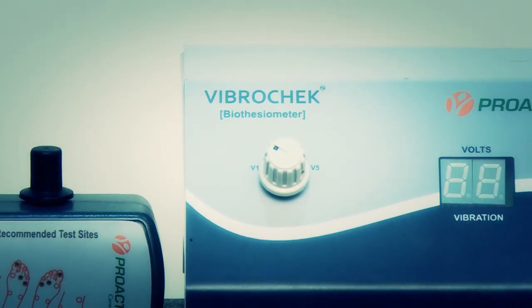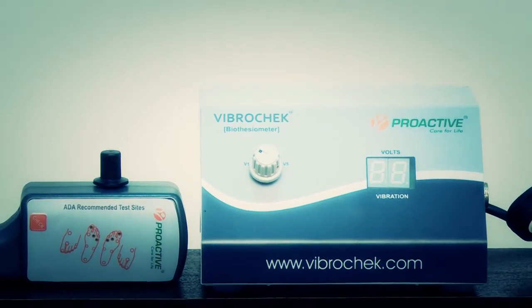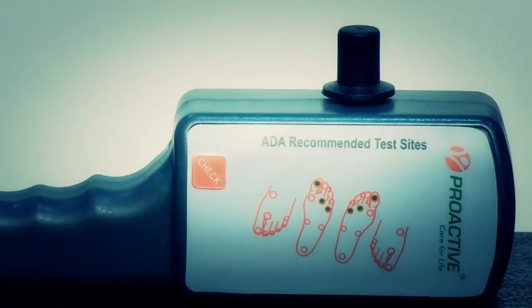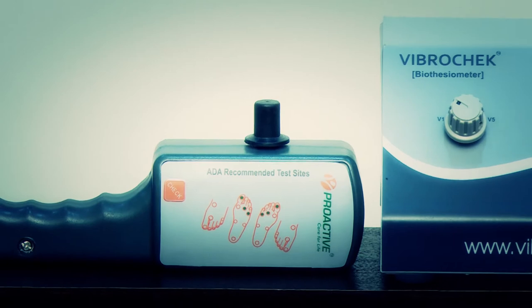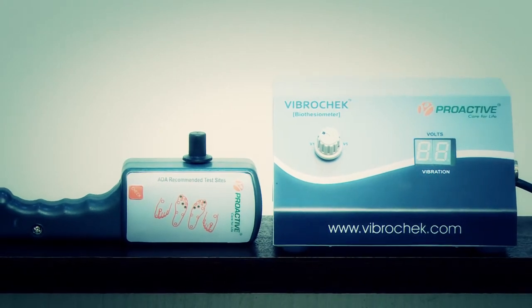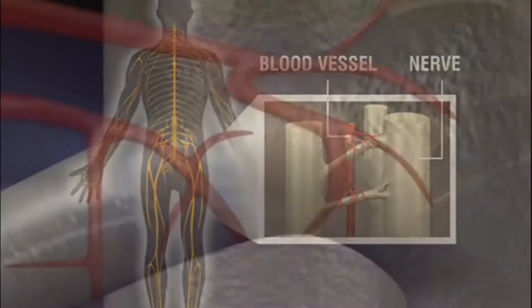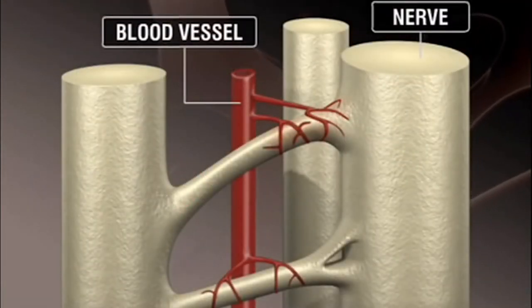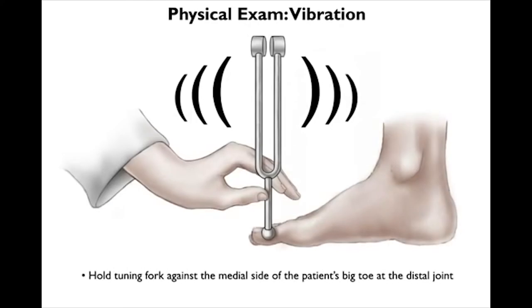Friends, here is a demo on the usage of Vibrochek, a digital biothesiometer. Vibrochek is brought to you by Proactive, a leading healthcare device company. Vibrochek can be called an electronic tuning fork that checks the level of neuropathy in a patient — normal, mild, moderate, and severe. Neuropathy is one of the most commonly occurring disorders due to idiopathic causes, genetic disorders, or metabolic and endocrine disorders. Vibrochek is especially helpful in checking diabetic peripheral neuropathy.